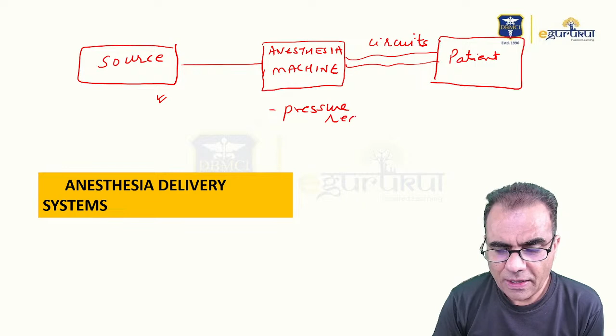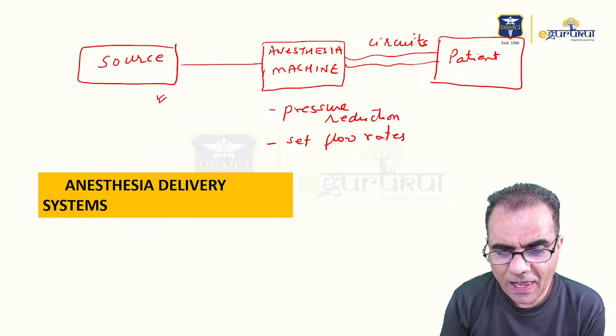So source. Now from source, gases will go to the anesthesia machine. And in the anesthesia machine, what happens? Three things that we do in the anesthesia machine. One will be pressure reduction. Pressure in cylinders and central supply is very high. It is not possible to give that much pressure, so we have to reduce the pressure. And how many liters of flow we should give, we can set that flow rate also. So we set flow rates. And third thing is we add a volatile agent.